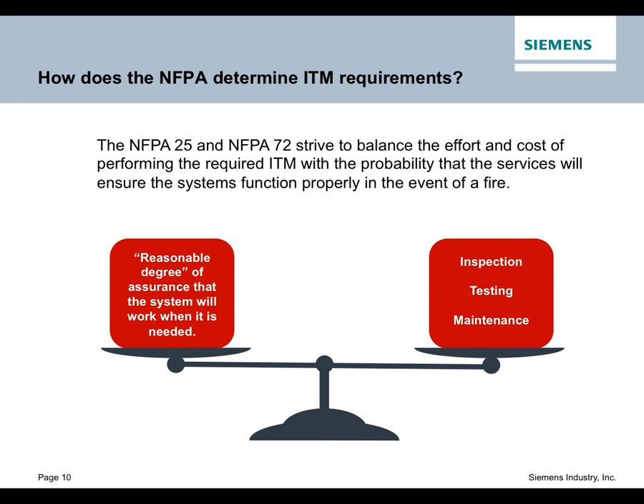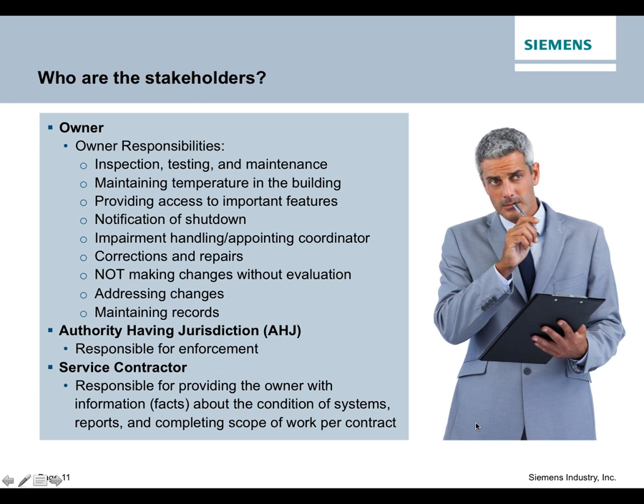So in other words, there's a lot of data behind this. When we take a look at the charts and you see that you need to test a water flow switch quarterly or semi-annually, and you need to test a control valve on a sprinkler system at a certain frequency, that stuff isn't just made up. It's done based on studies and research, and is looked at and reviewed every 3 years for possible change. The purpose is to provide an overall reasonable degree of protection through the minimum amount of inspection, testing, and maintenance. It's worth restating the fact that all of these standards are minimum.